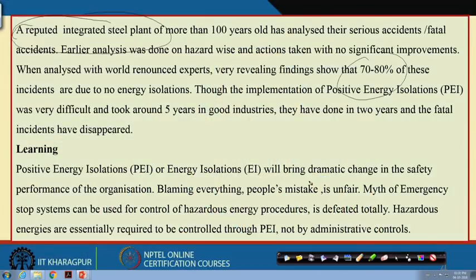So what is the learning? Positive energy isolation will bring a dramatic change in the safety performance of an organization. Blaming people — saying people make mistakes, people are careless — is very unfair. There is also a myth that we have emergency stop systems and can use them when required; the purpose of emergency stops is different. Hazardous energies are essentially required to be controlled through positive energy isolation, not administrative controls — not warnings, not signages. They are to be controlled by engineering means of isolation, not administratively.